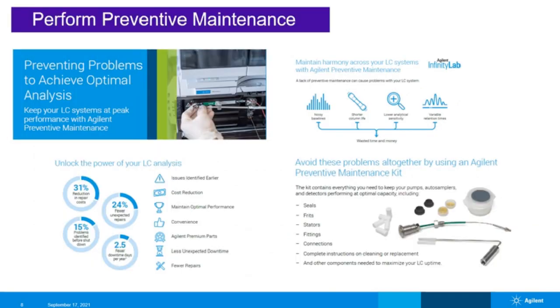Why performing preventive maintenance? Chromatographic symptoms visible with a change in peak shape or a change in pressure or ripple or noise are forerunners for issues on your LC system. Regular maintenance on your system with exchange of wearing parts like needle seat, rotors, frits or seals before they are damaged is the right approach to achieve optimal analysis. We see here that regular maintenance helps to identify problems before a shutdown, reduce by 24% unexpected repairs, and lower by 31% the repair costs. A recent 5-year study with more than 38,000 service calls has estimated a 2.5 fewer downtime days per year when doing regular maintenance on an LC system.